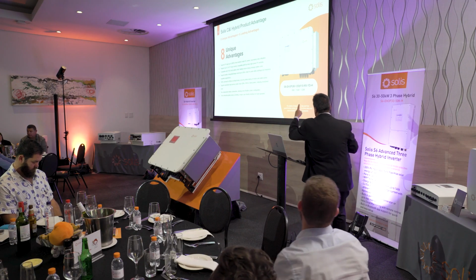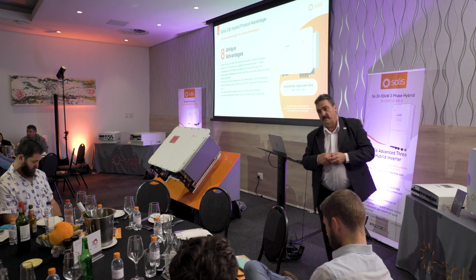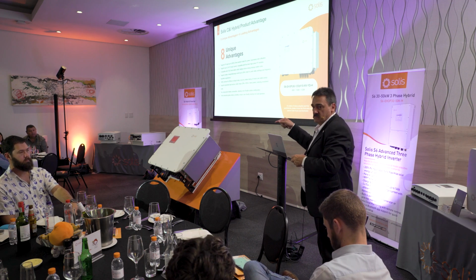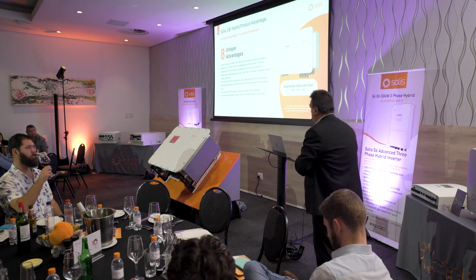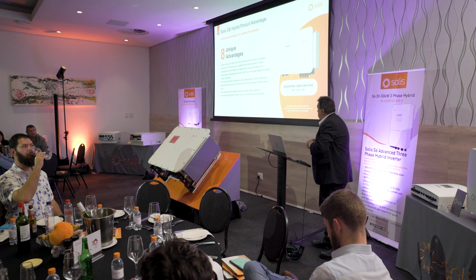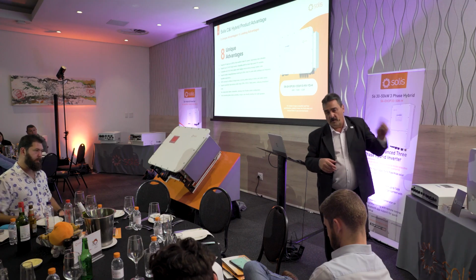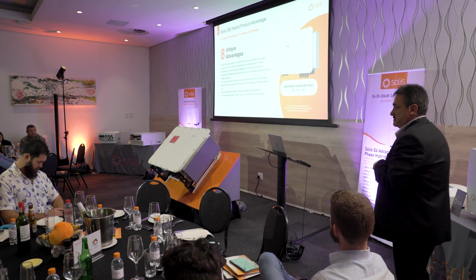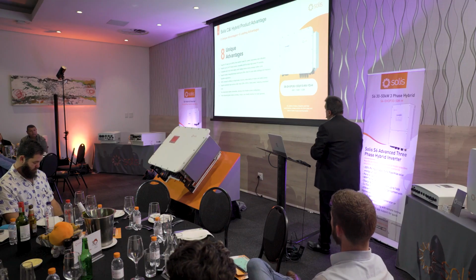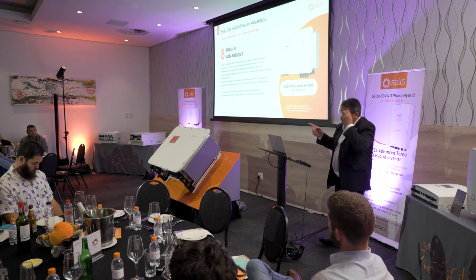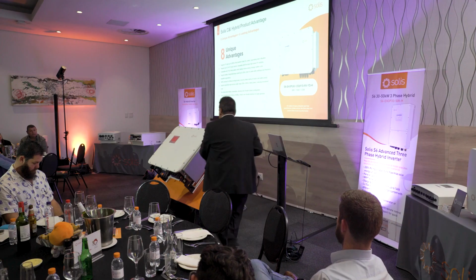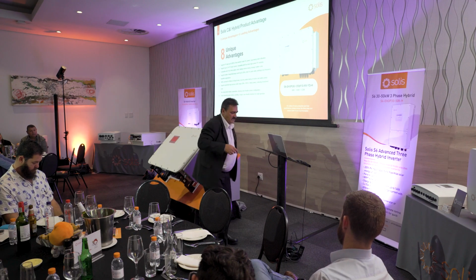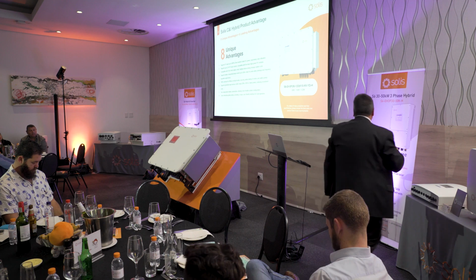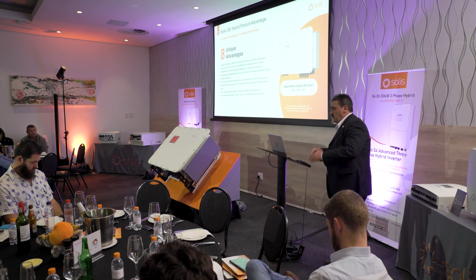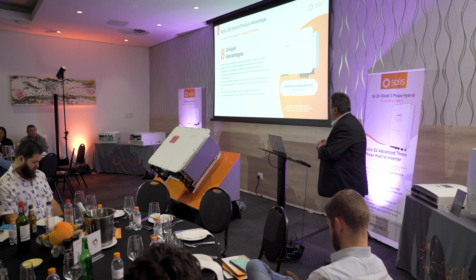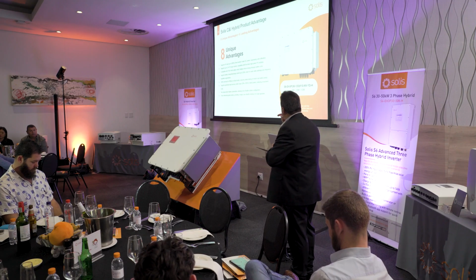As mentioned, all the strings are 21 amps load current, not short circuit, which is a bit higher. It's compatible with 100 to 314 amp hour battery systems, supporting discharge and charge current up to 200 amps, across 2 ports at 100 amps each, with battery bank voltage up to about 950 volts. So there's lots of power to be had.